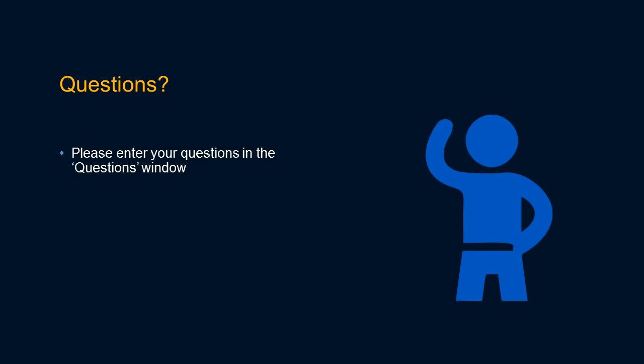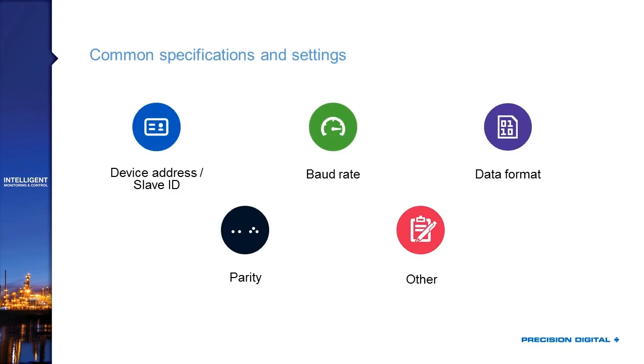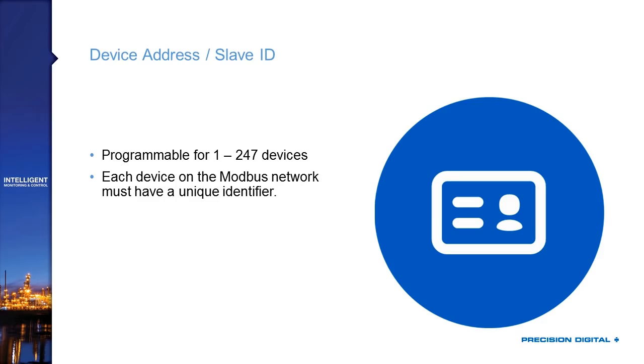To understand what Modbus is really doing, you need to understand some terminology. You have to be familiar with slave address or device ID, baud rate, data formats, and parity. There are other specifications as well, though most aren't necessary for a basic setup. Every Modbus device must have a device address — sometimes called a slave ID — which is a unique identifier on the Modbus network, a number between 1 and 247.